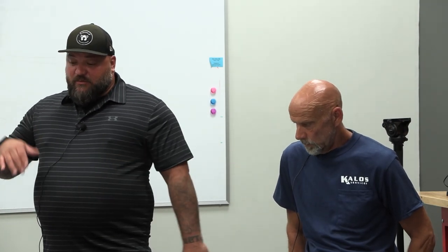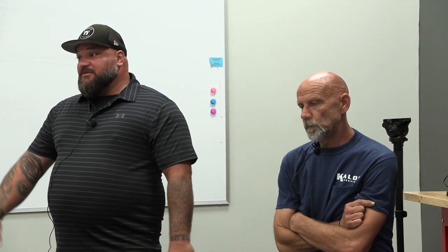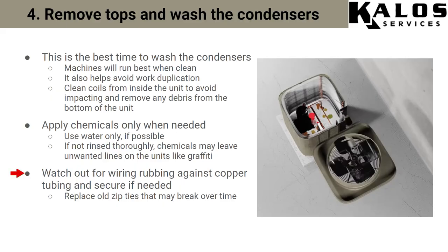While you're doing that, watch for fan wires or compressor wires laying on top of the suction line or discharge line. When putting it back together, if you notice wires with little pits from rubbing, make sure you get them insulated away. The zip ties currently holding high voltage and low voltage wires together will break, and the majority of units have wire resting against copper that is beginning to rub out. It takes two seconds to get a zip tie and strap those back up — both high and low voltage. We're there every six months, so cut the previous zip tie off and put a new one on. We want to protect against rub-outs.